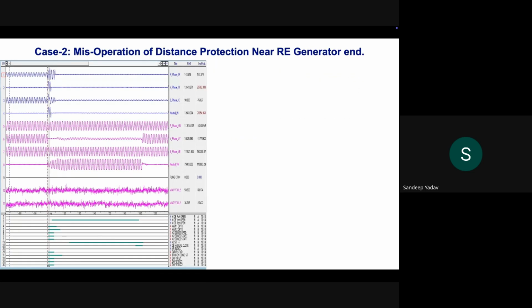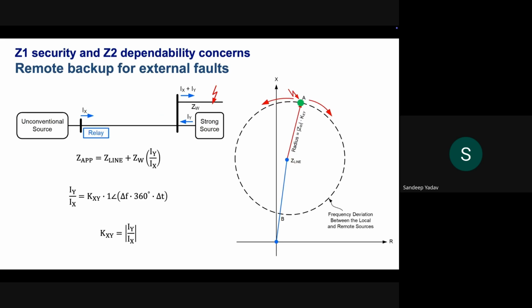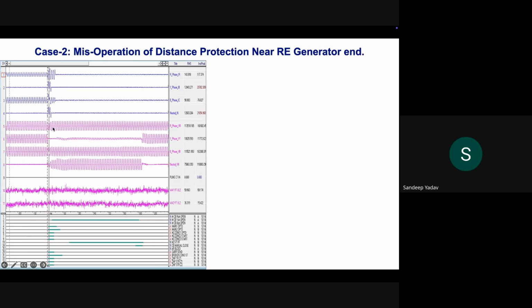Now, for example, the distance relays which are located here at the RE generator end, the magnitude that they see is very small. So IX is very small, right? So it may be very difficult for these distance relays to operate onto the fault. So if you take a look at this, these are the R, Y, and B phase currents, and this is the grid side.